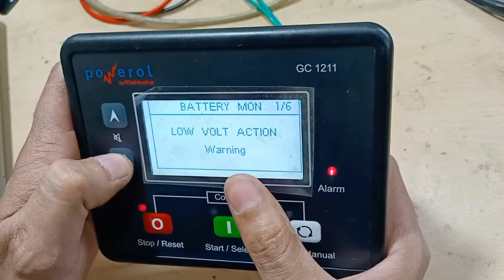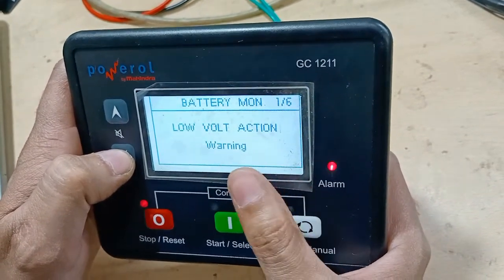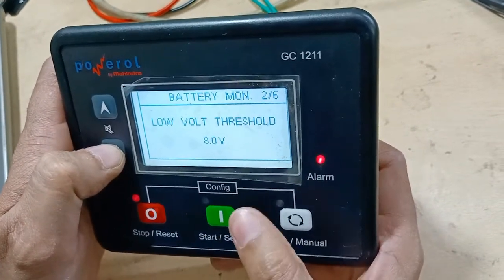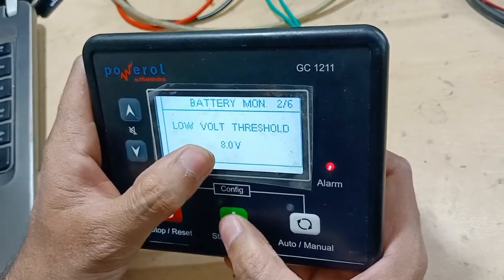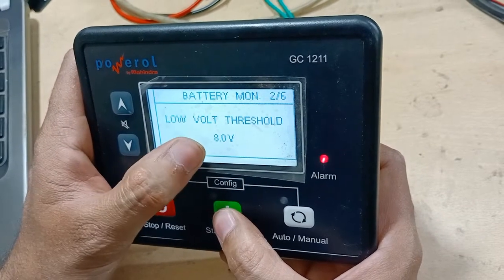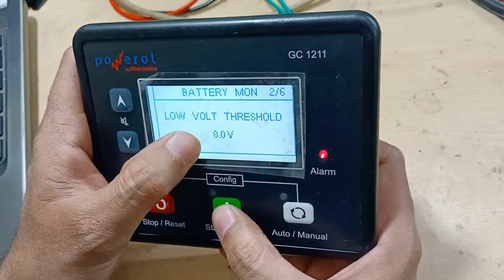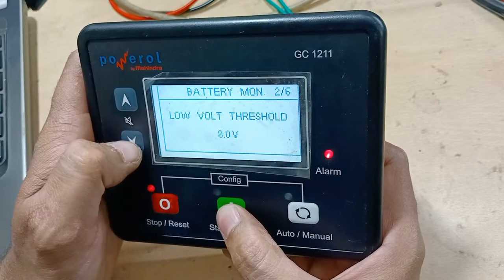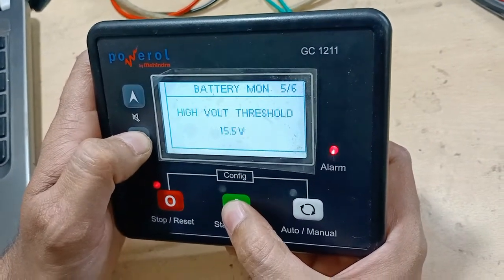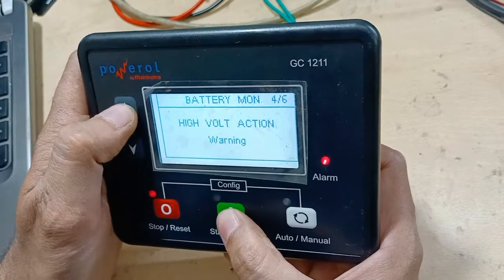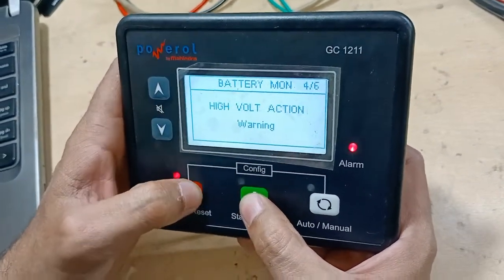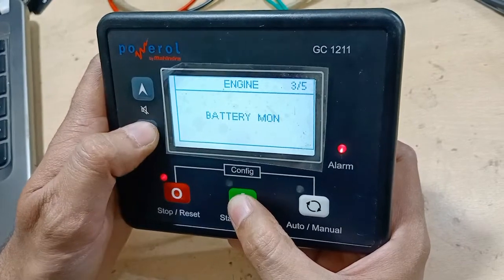If the battery voltage falls below the threshold, you can configure whether it gives a warning, a notification, or a complete shutdown. For example, if battery voltage goes below 8 volts, the engine will automatically give a shutdown command and stop after a 30-second delay.